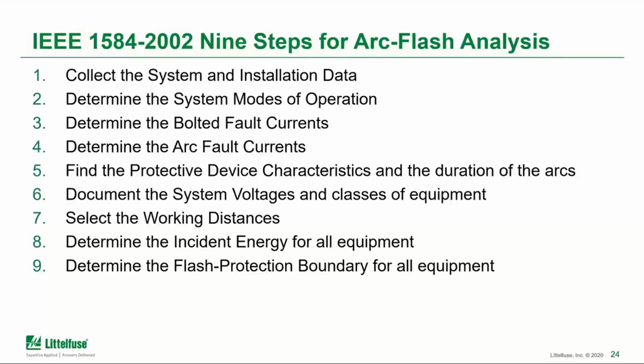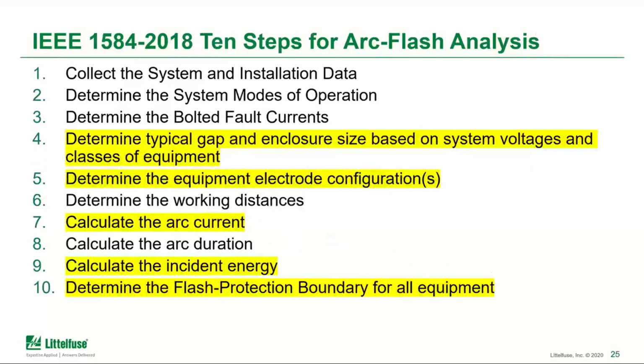And second, looking at the modes of operation. So here, this is deciding or understanding, do you have alternate or standby sources that need to be included? Do you have tiebreakers? Are they going to be open or closed? And whether motors are considered to be running or de-energized at the time of arc. So those are things that go into the mode of operation. And from there, you progress to do the bolted fault currents, the arc fault currents, look at the protective device characteristics that you have in the system, document the system voltages, and select the working distances, and finally the incident energy and the protection boundaries.